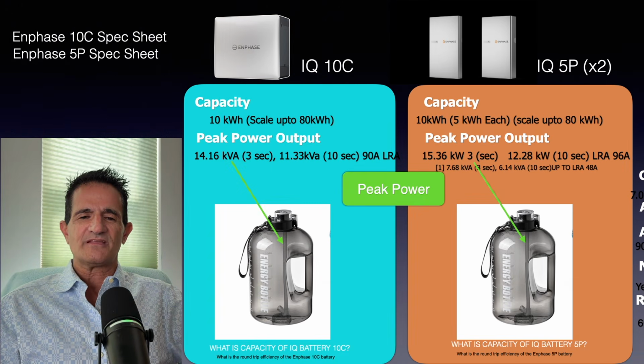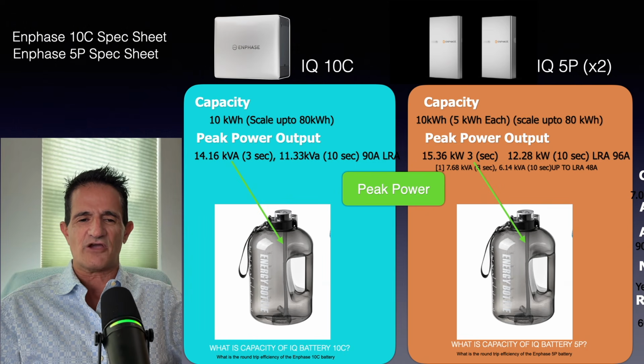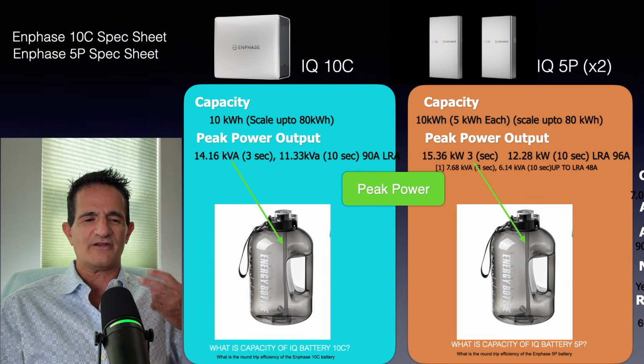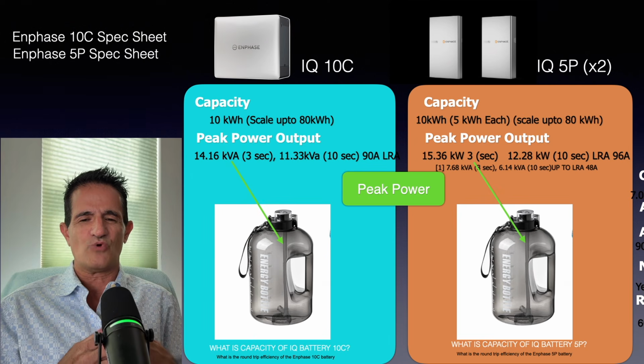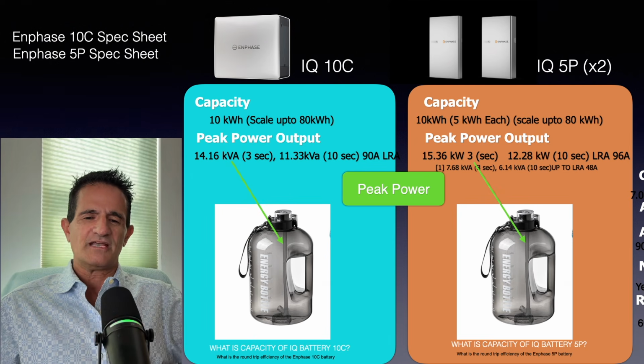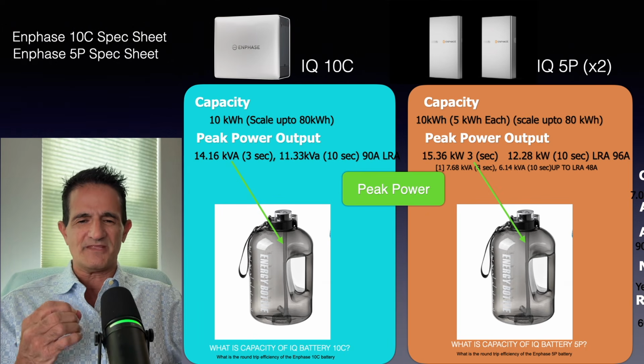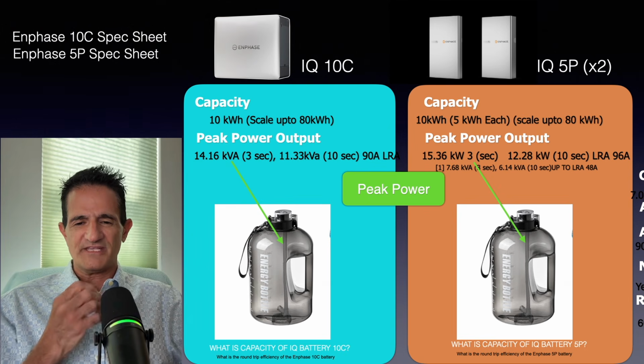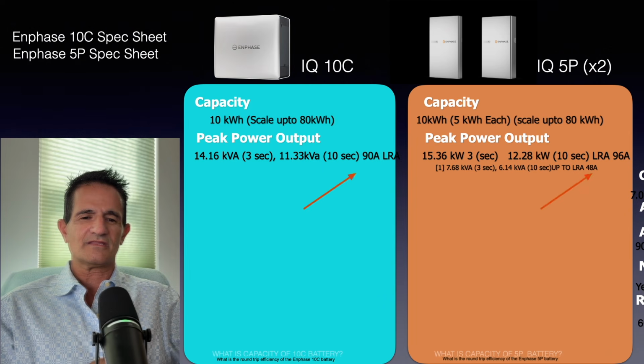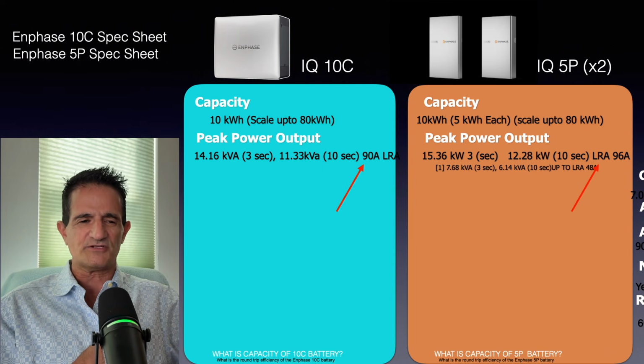So for the 10C, the peak power output is 14.16 kVA for 3 seconds, 11.33 kVA for 10 seconds, and 90 amps LRA. For the 5P, it's 15.36 kVA for 3 seconds, 12.28 kVA for 10 seconds, and LRA of 96 amps. Again, this is for 2 of the 5P batteries. And by the way, that's most likely, most people aren't going to get one 5 kW battery. That's not enough to do much. And so the peak power output, again, is for when you're trying to run something with a big surge, like a heat pump, air conditioner, pool pump, things with a motor. LRA is to run heat pumps or air conditioners.